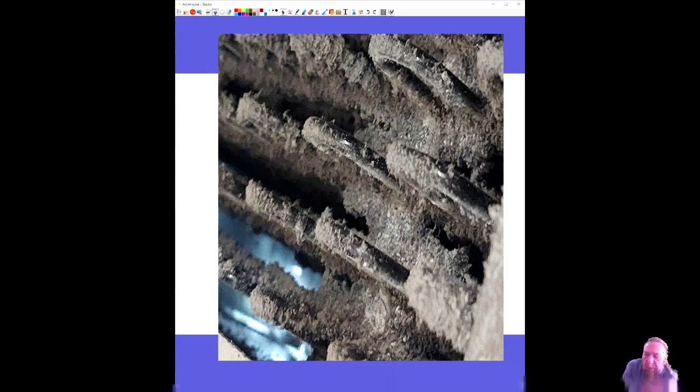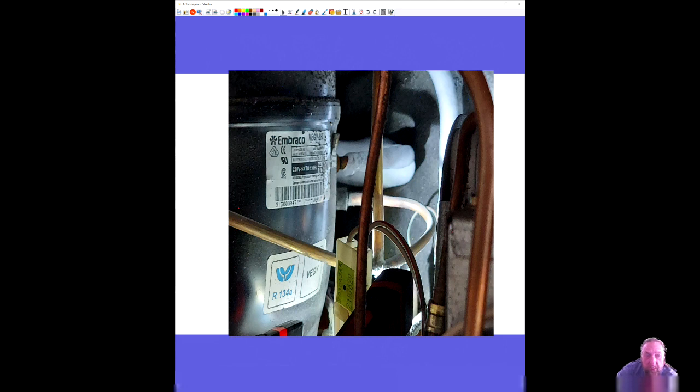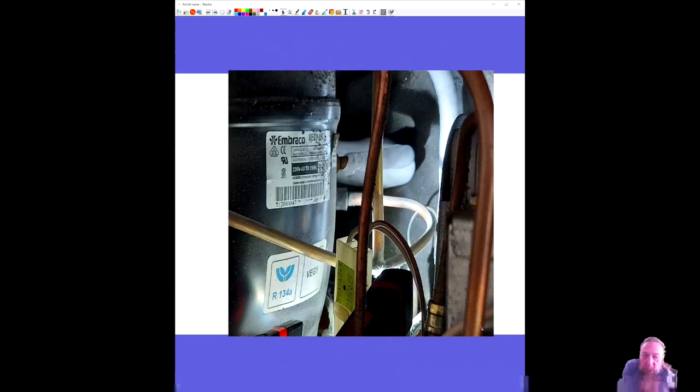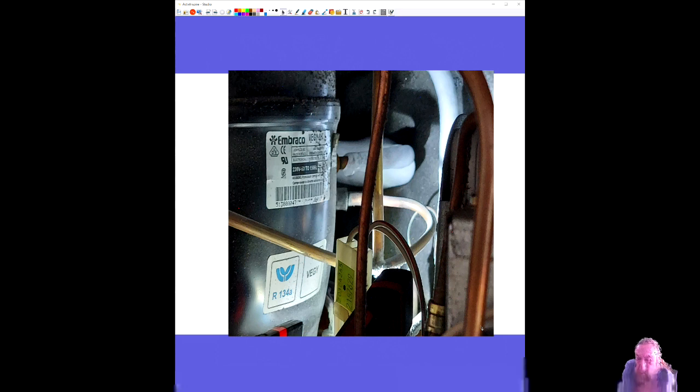ice like that, you want to look at the evaporator. First thing I want to do is check the defrost cycle. But seeing all that dust on this condenser, on this compressor, and then seeing the picture of this condenser, what problem is going to happen from this dirty condenser? It's gonna cool worse, less cooling, because some of the high head refrigerant pressure is going to be vapor when it enters the evaporator. You're gonna have a high head pressure.